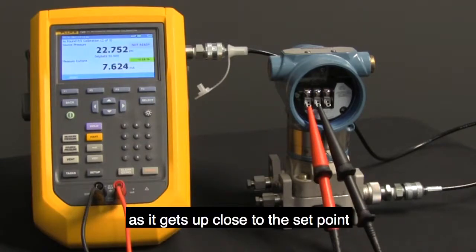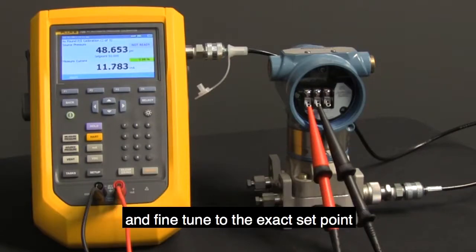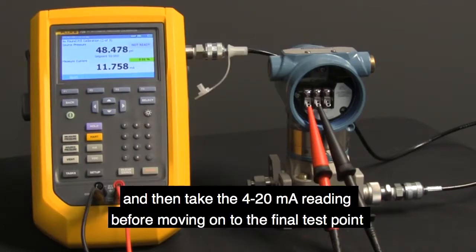As it gets up close to the set point, you'll notice the pressure will stop and then the automatic regulator will kick in and fine-tune to the exact set point. Hold on to it for the three second delay we put in and then take the 4 to 20 milliamp reading before moving on to the final test point.